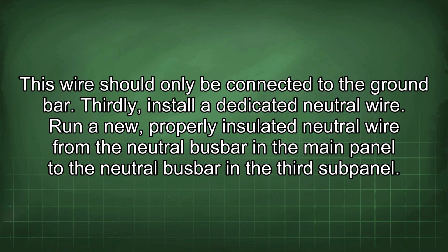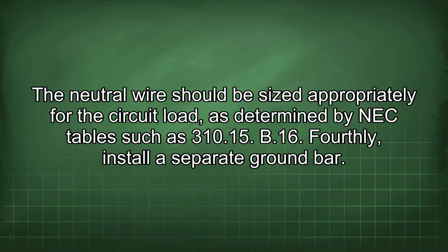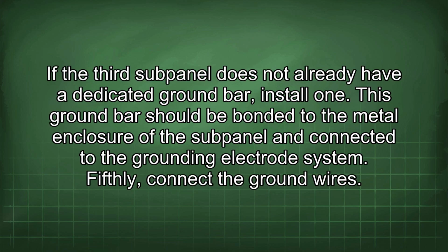Run a new, properly insulated neutral wire from the neutral busbar in the main panel to the neutral busbar in the third subpanel. The neutral wire should be sized appropriately for the circuit load, as determined by NEC tables such as 310.15(B)(16). Fourthly, install a separate ground bar. If the third subpanel does not already have a dedicated ground bar, install one. This ground bar should be bonded to the metal enclosure of the subpanel and connected to the grounding electrode system.